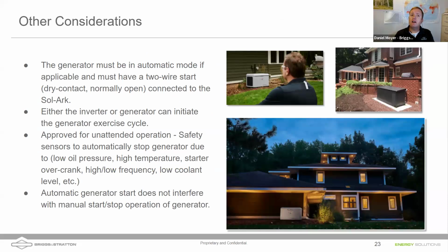So again, what kind of generators can be used? It has to be one that has automatic start with the normally open signal. It's important to understand that either the inverter or the generator can initiate that exercise cycle. These portables, usually all the ones that do have the 2-wire signal to start, are going to be approved for unattended operation. They have features so that if it runs out of oil or gets too hot, or isn't firing, it'll shut itself off and protect itself.